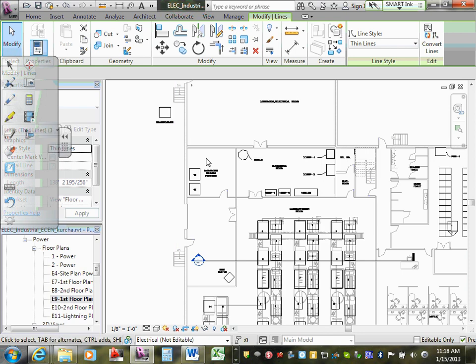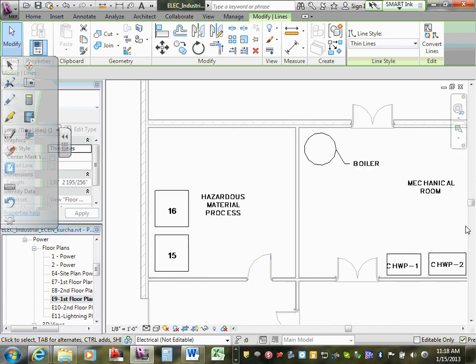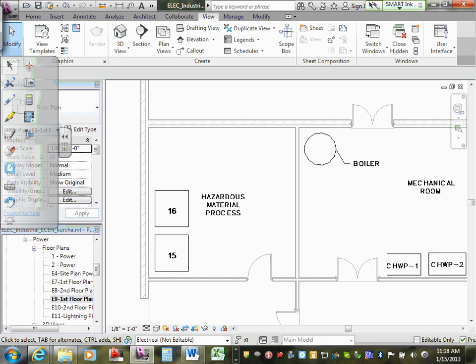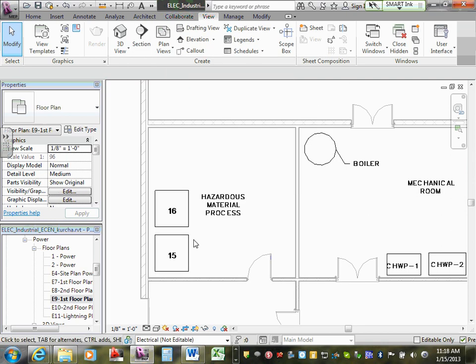Again, that's the Class 1 Div 1. You're going to have the smoke detector. You're going to have the Class 1 Div 1 strobe beacon, and then the Class 1 Div 1 horn. And that's all going to be a separate run in. Any monitoring that has to happen in here goes through the intrinsically safe barrier. The monitor module is usually out here, outside of the room, with everything running inside. Usually you're going to put an isolation module after the monitor module to isolate any sparks or any surges that will be going through. But typically everything will be mounted outside.